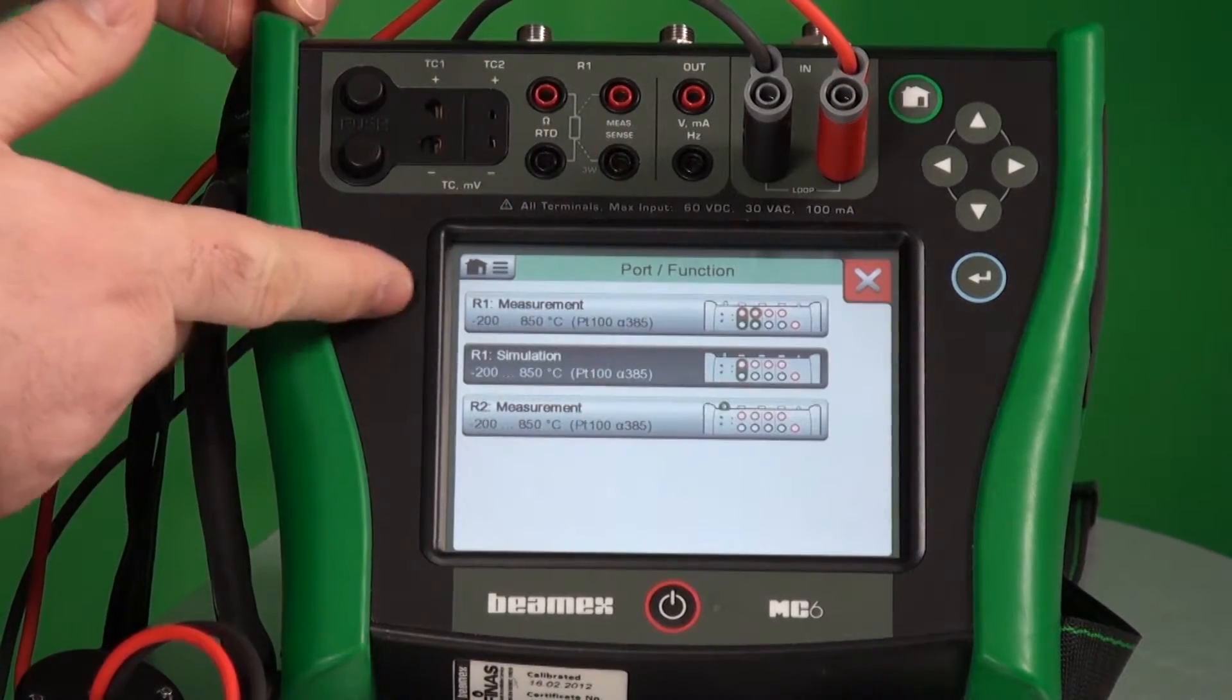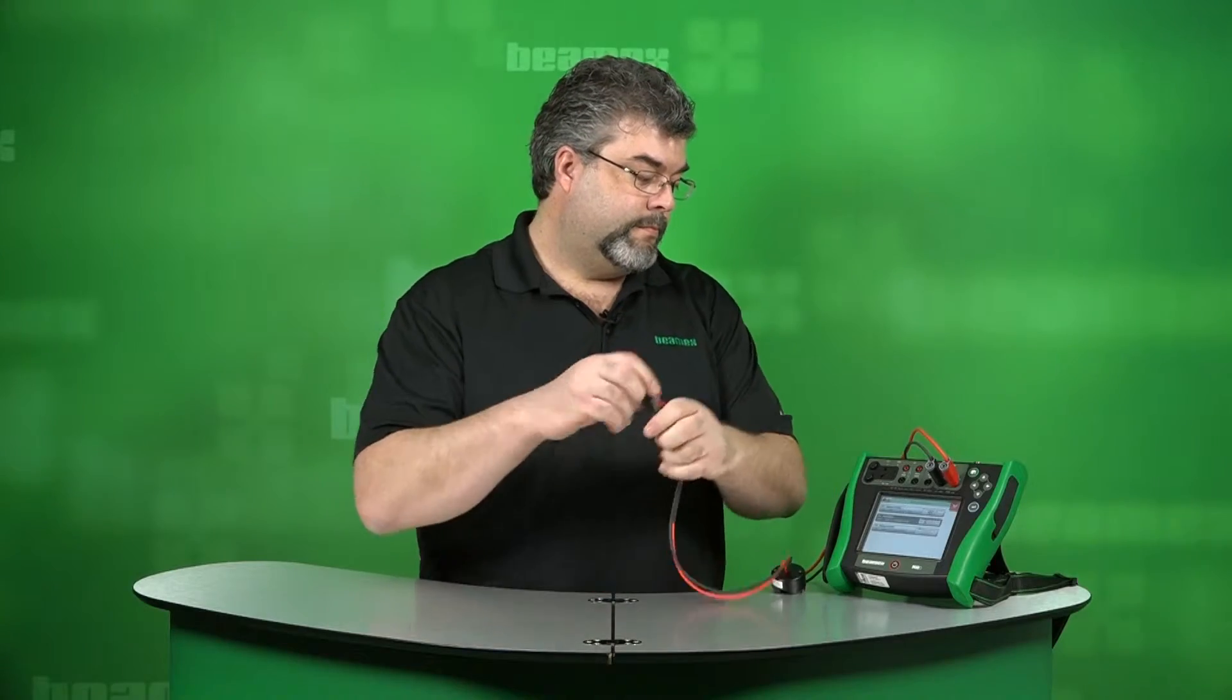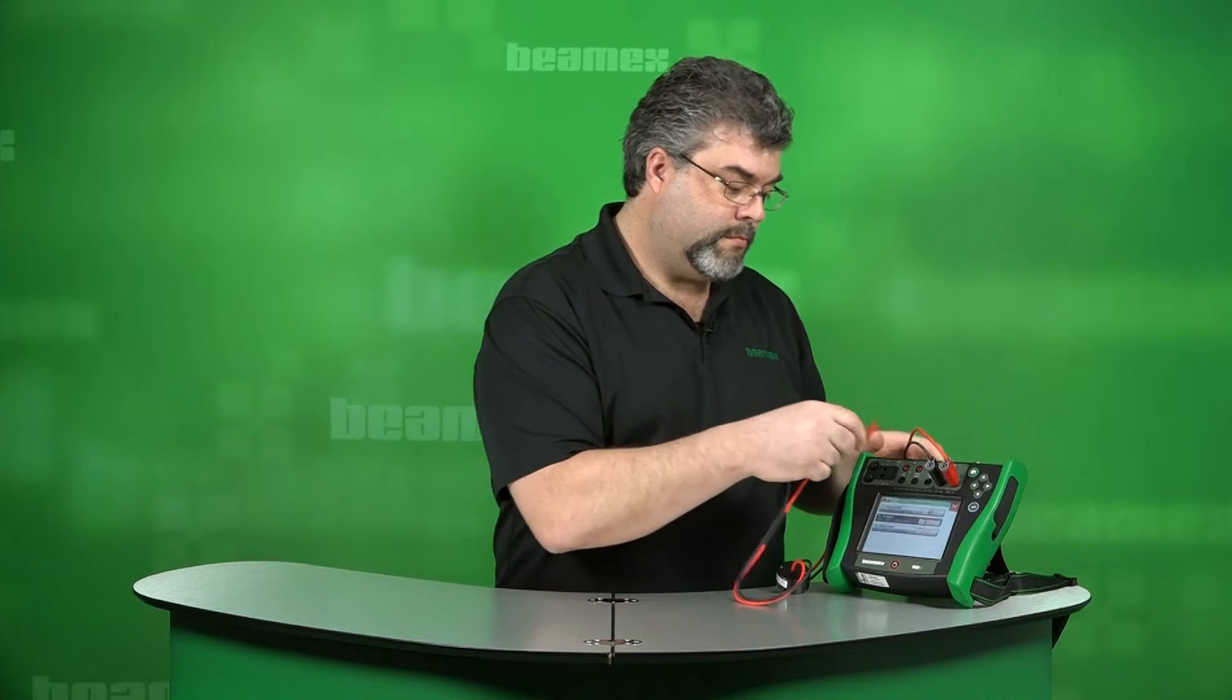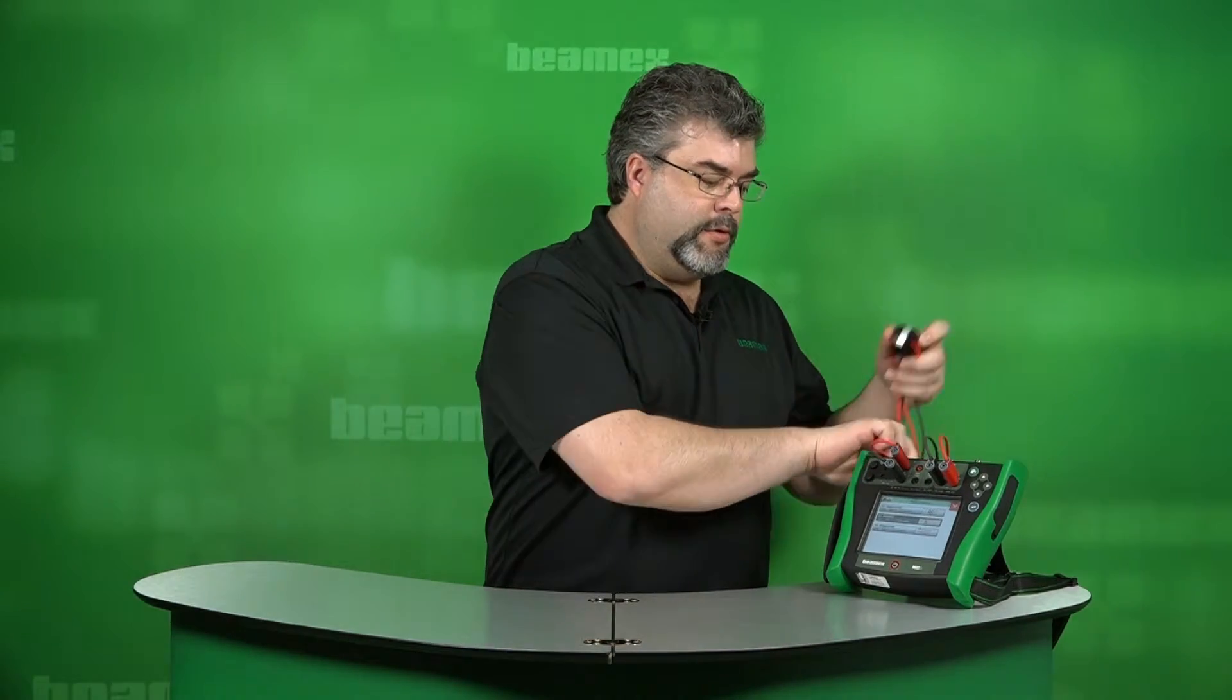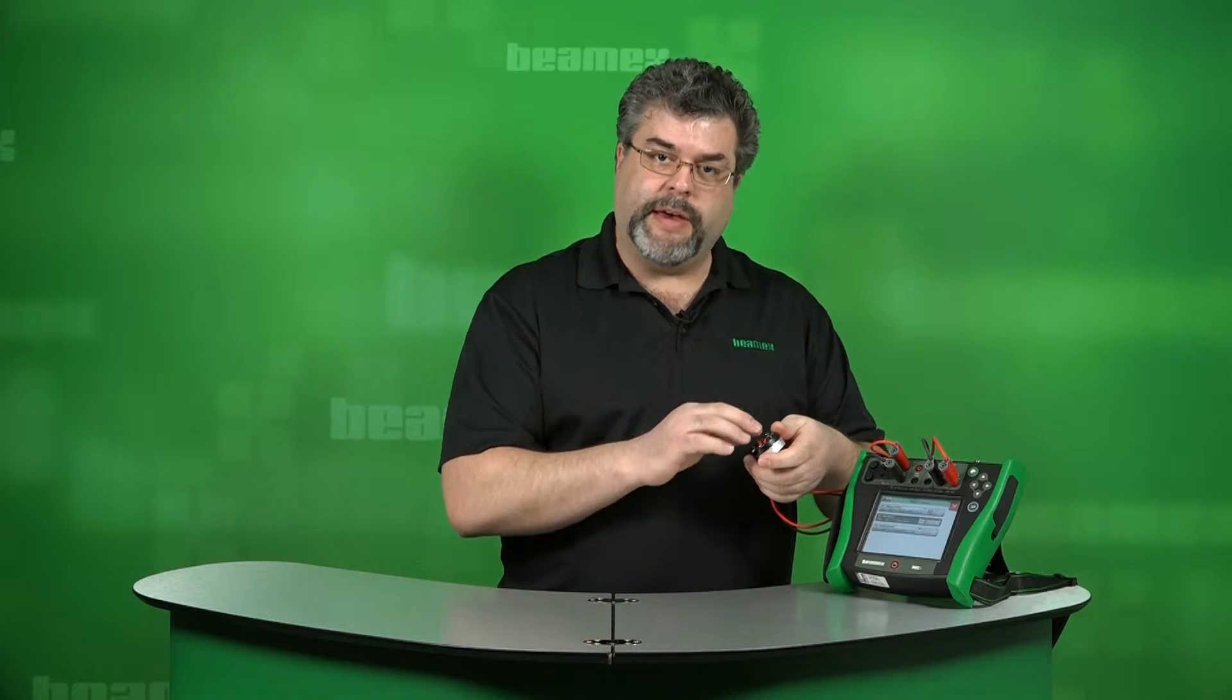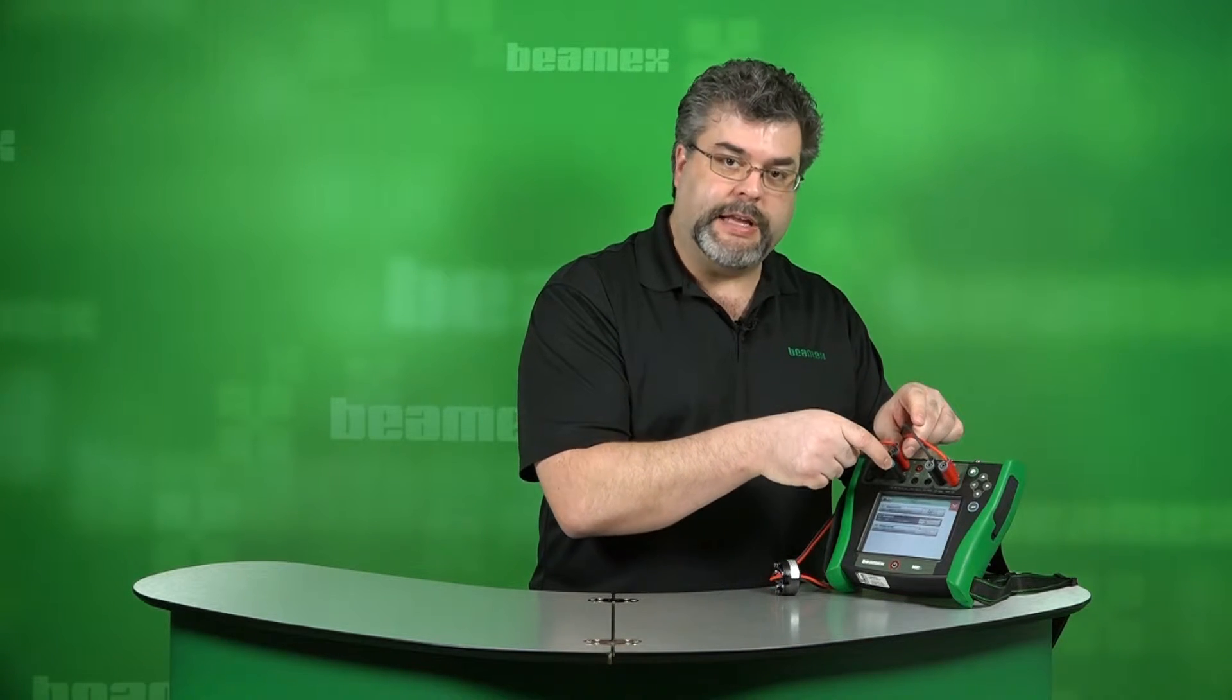Now on my input, I wasn't paying attention to know where to plug in. So if we go back up here to simulation, this shows you where to plug in to simulate RTD. You'll notice that I'm plugging in two leads. This is actually a four-wire RTD, but behind the scenes here, we've actually doubled up a couple of the wires just to make it easier for my demo. But if you had a four-wire RTD and you had four leads, you simply stack the two reds on top and then stack the two blacks.